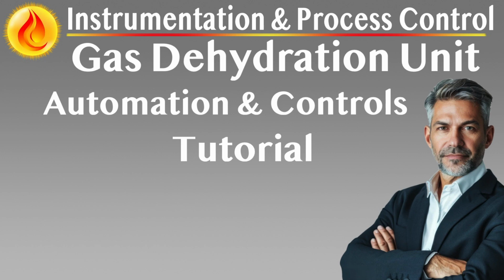Diagnostic and maintenance enhancements. HART protocol and digital diagnostics. All smart transmitters support HART Fieldbus for live status feedback, remote diagnostics, and auto-calibration features. Integrated alerts for sensor drift, signal degradation, or calibration errors. Self-test and loop check routines. Periodic auto-verification routines confirm integrity of signal paths, especially during system initialization or maintenance cycles.